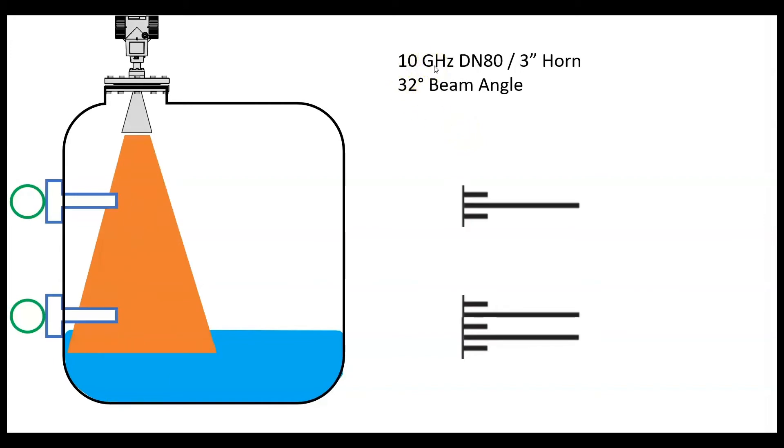A typical 10 gigahertz radar with a 3-inch horn would have a 32-degree beam angle. Why that's important is you get a nice wide coverage, but it can also pick up what we would consider false echoes.